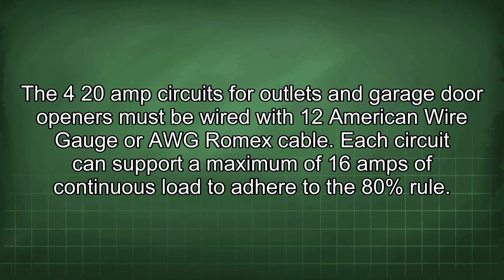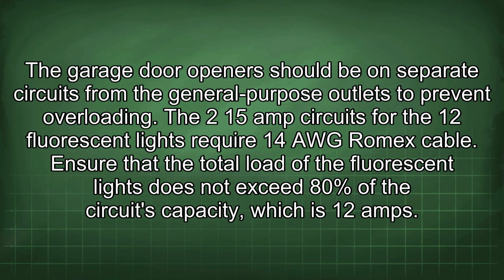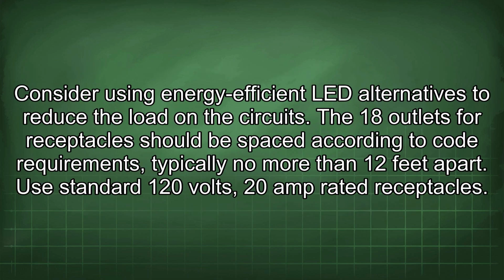The 4 20 amp circuits for outlets and garage door openers must be wired with 12 American wire gauge, or AWG, Romex cable. Each circuit can support a maximum of 16 amps of continuous load to adhere to the 80% rule. The garage door openers should be on separate circuits from the general purpose outlets to prevent overloading. The 2 15 amp circuits for the 12 fluorescent lights require 14 AWG Romex cable. Ensure that the total load of the fluorescent lights does not exceed 80% of the circuit's capacity, which is 12 amps. Consider using energy-efficient LED alternatives to reduce the load on the circuits.